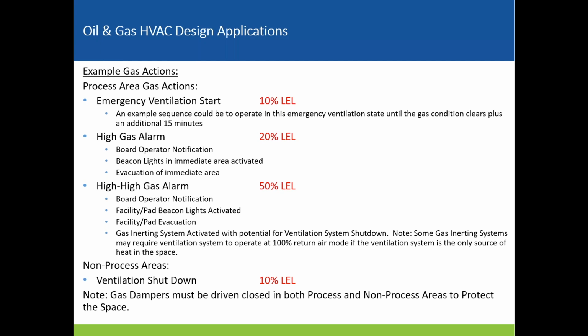And then if that doesn't work, we're going to go to our high gas alarm, and that's where it's going to go to the board operator. We'll set off the beacon lights, and the evacuation of the needed area. If we keep going up to that 50% LEL, that's when the facility and pad evacuations could begin. Have gas inerting systems, those can be activated.